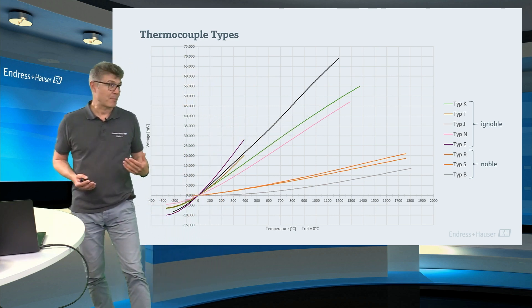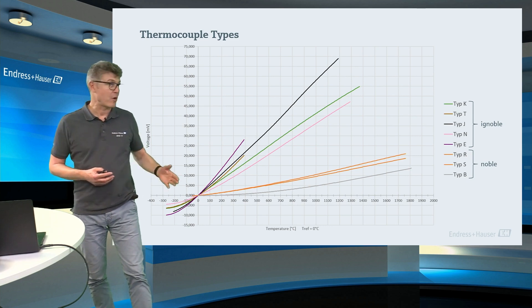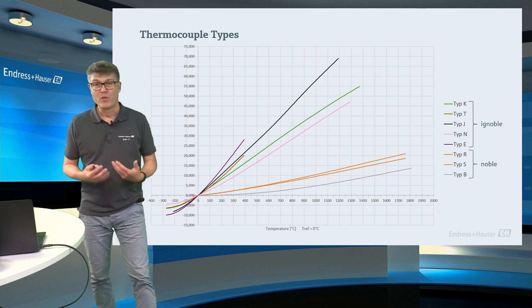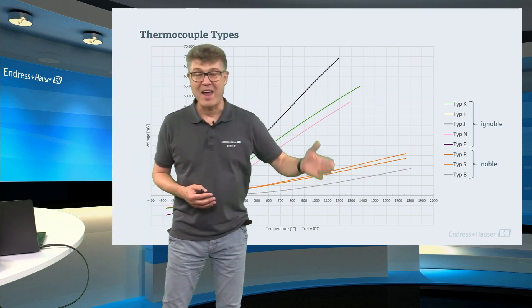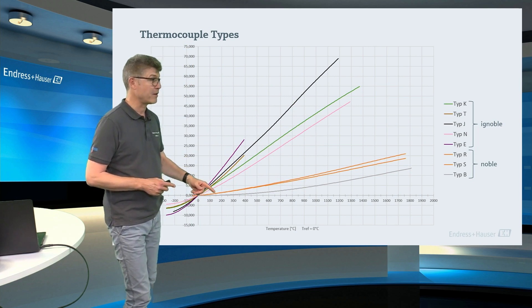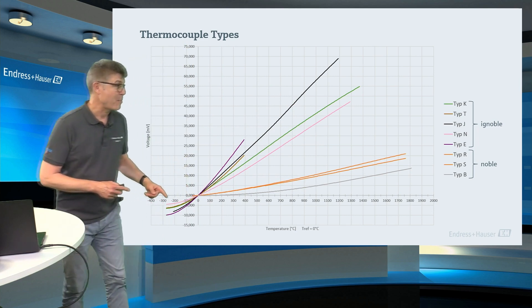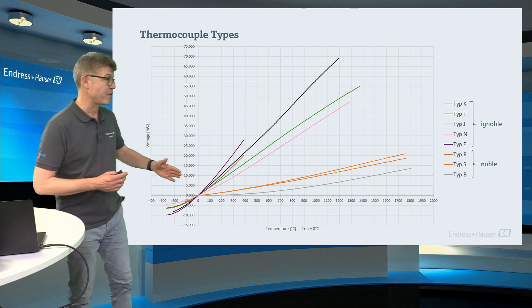For higher temperatures, chrome-nickel is not suitable any longer. You have to go to noble thermocouples, which is typically platinum. Platinum together with rhodium. The most popular here is type S. Type S is platinum on the one side and platinum and rhodium on the other side.